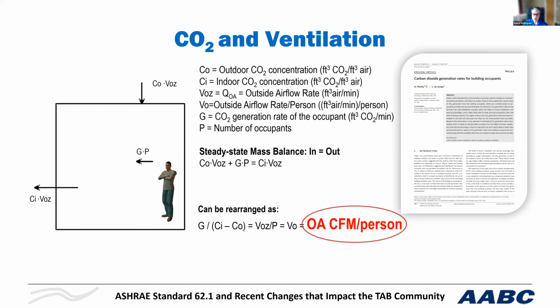And it's also important to note that CO2 is a lagging indicator. It lags because it has to fill up the space. You have a large volume of space, and it takes longer for the CO2 from people breathing, as I'm speaking now and pushing out CO2, to fill that space. And as you bring ventilation into the space, you're diluting the CO2 that's building up. And there's actually CO2 in the outside air, somewhere between 350 and 450 ppm, depending where you are on the planet. This buildup may take an hour or even more than an hour to reach steady state, and that's assuming that people don't leave or come into the space, because that changes the equation.